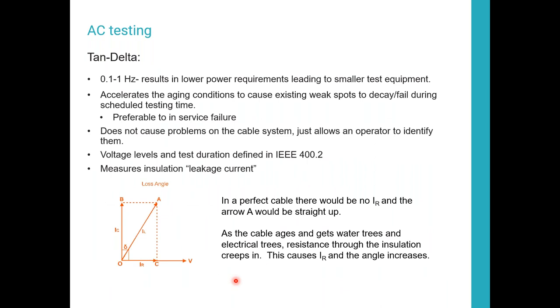Another form of it is a tan delta test. It uses a very similar test setup as the very low frequency, so it's a 0.1 to 1 hertz test. Many times the tan delta test is an option in the very low frequency test set. It accelerates the aging conditions, causes existing weak spots to identify themselves during testing, very similar to VLF, and doesn't cause problems on the cables.